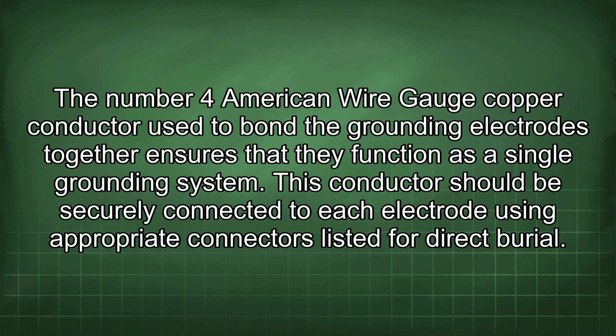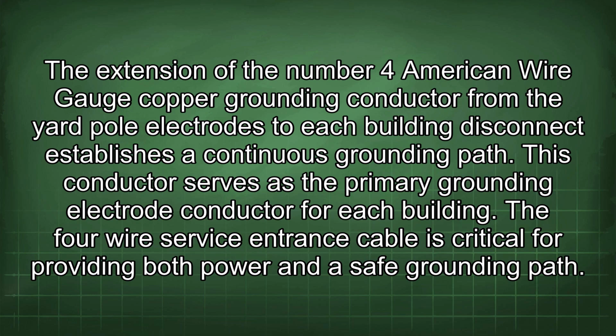The number 4 American wire gauge copper conductor used to bond the grounding electrodes together ensures that they function as a single grounding system. This conductor should be securely connected to each electrode using appropriate connectors listed for direct burial. The extension of the number 4 American wire gauge copper grounding conductor from the yard pole electrodes to each building disconnect establishes a continuous grounding path. This conductor serves as the primary grounding electrode conductor for each building.